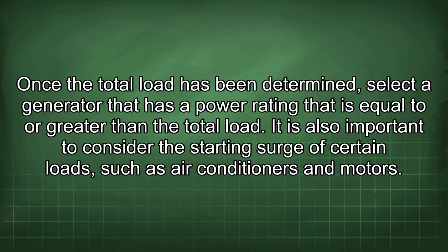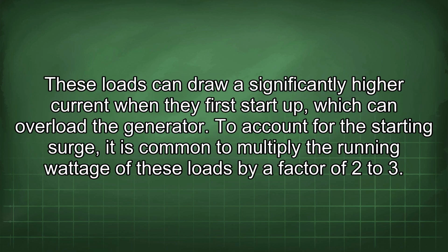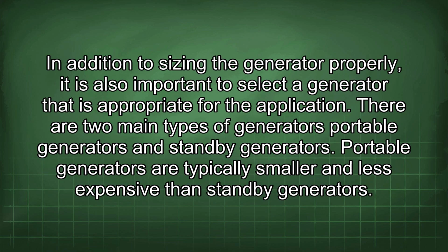It is also important to consider the starting surge of certain loads, such as air conditioners and motors. These loads can draw a significantly higher current when they first start up, which can overload the generator. To account for the starting surge, it is common to multiply the running wattage of these loads by a factor of 2 to 3. In addition to sizing the generator properly, it is also important to select a generator that is appropriate for the application.